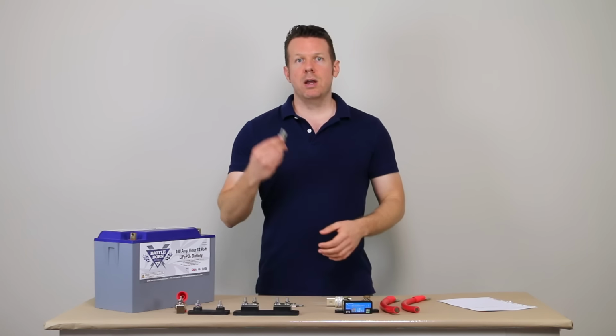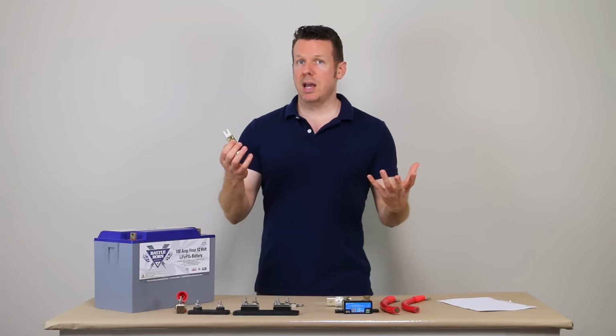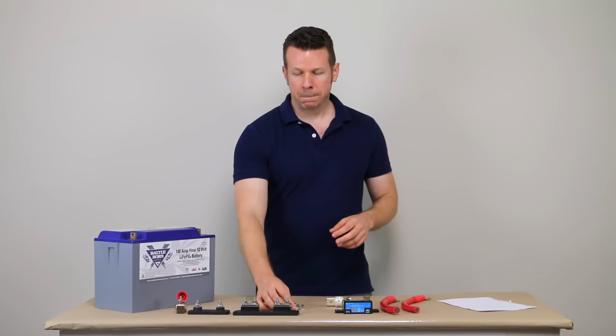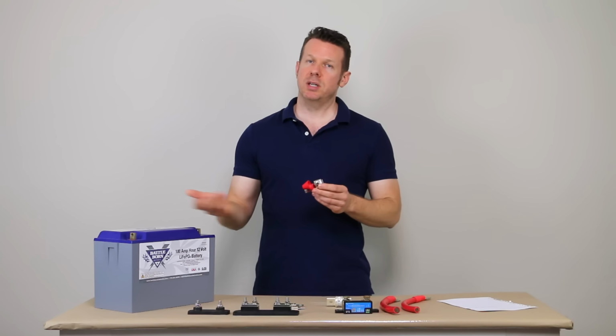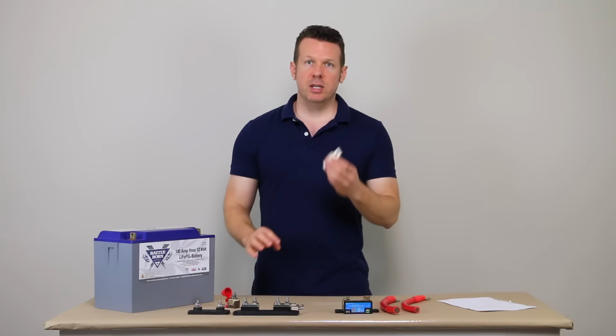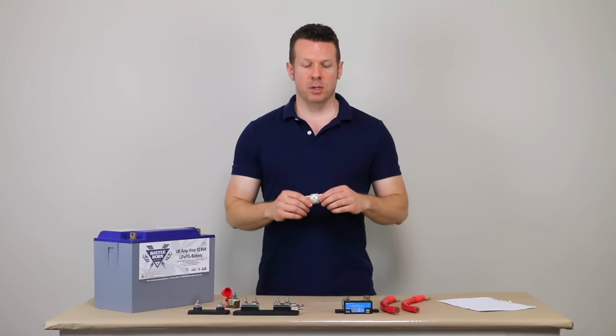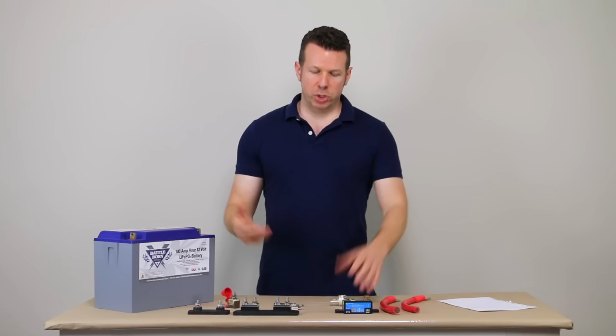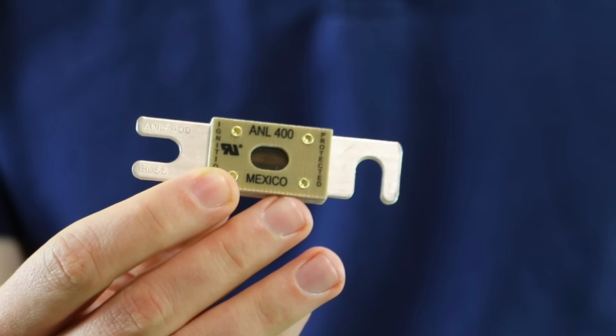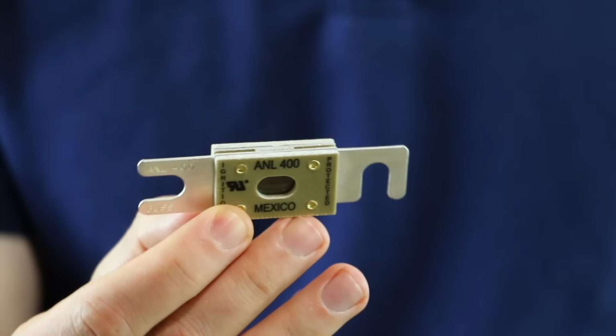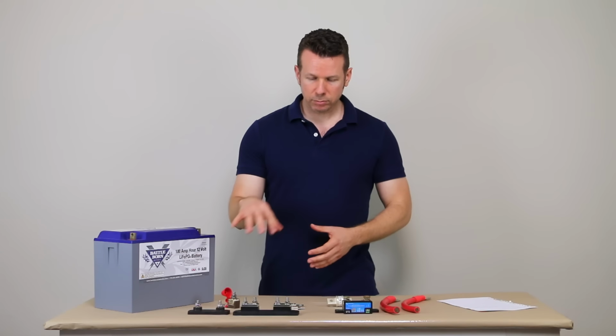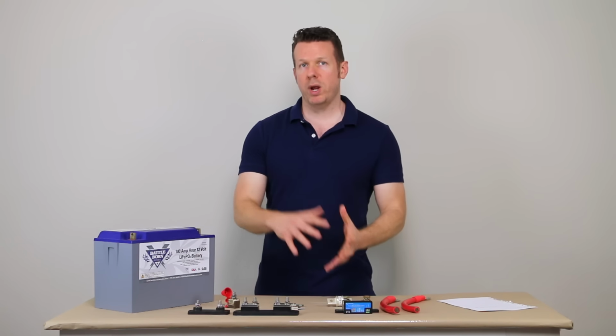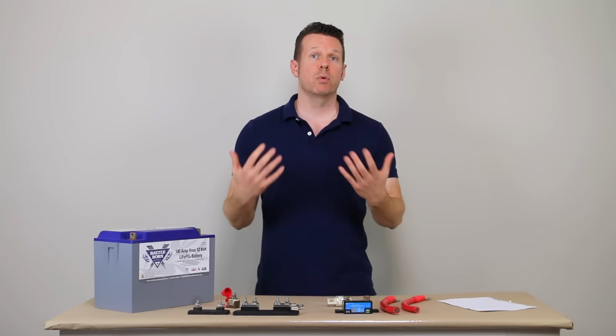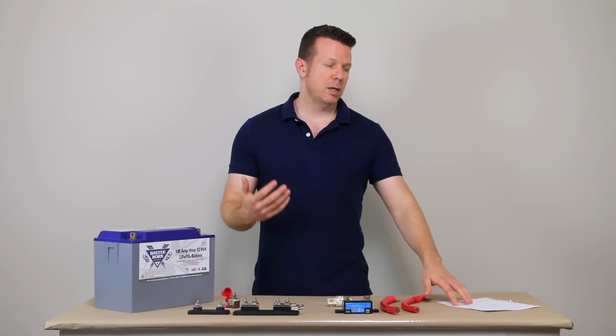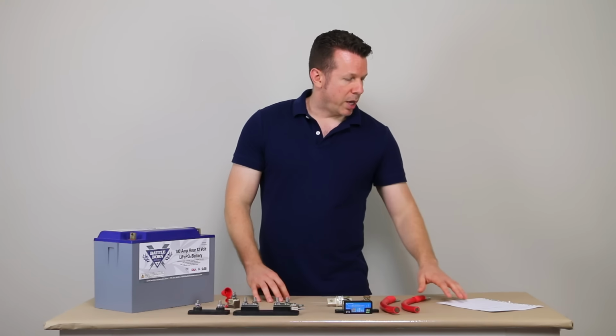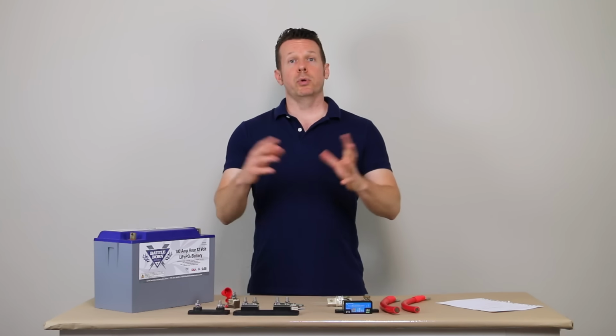For instance, the ANL fuse can interrupt up to 6,000 amps coming out of the batteries. The terminal fuse can interrupt up to 10,000 amps. And the Class T can interrupt up to 20,000 amps. So my go-to is going to be a 400 amp ANL fuse. I'll just tell you that. But that's why they are rated as main battery fuses, that interrupt current ability. So let us move on to mistake number 6, loose connections.